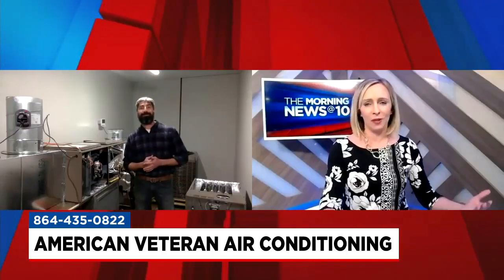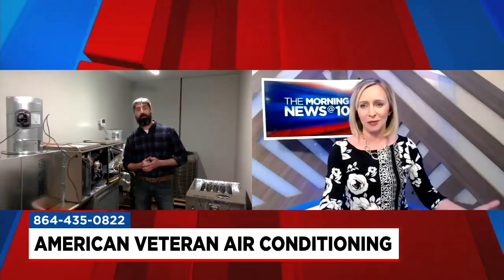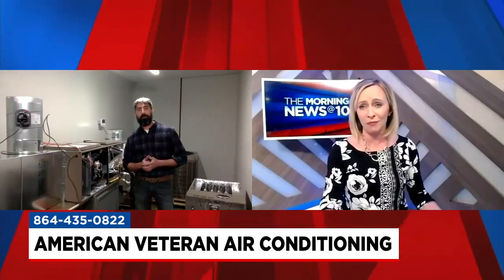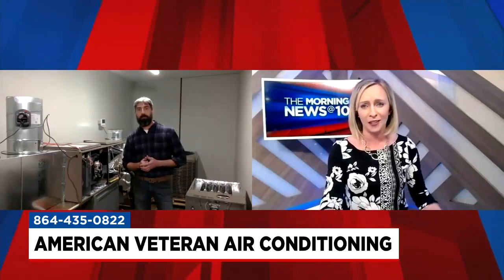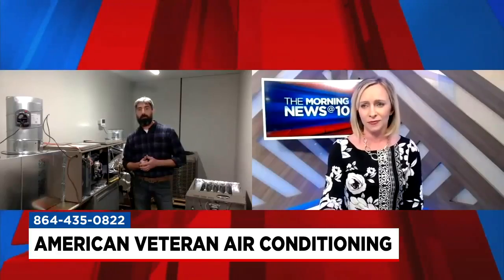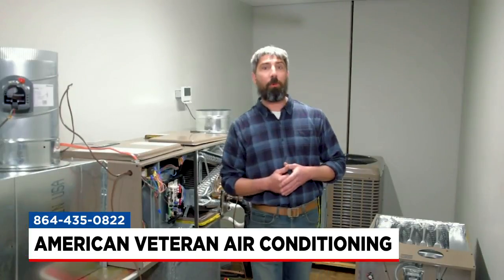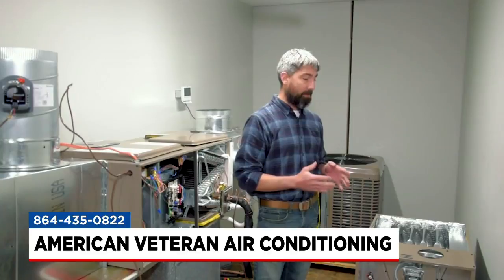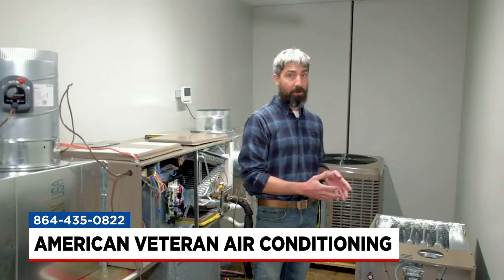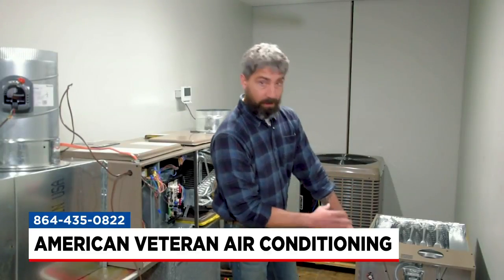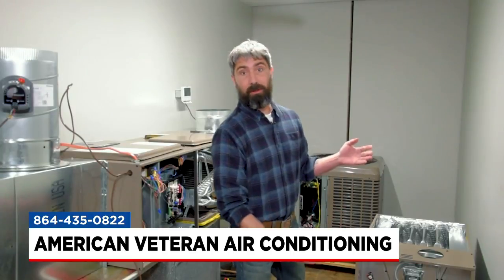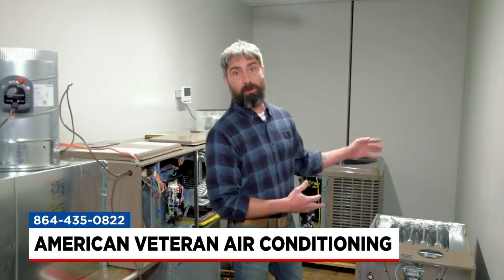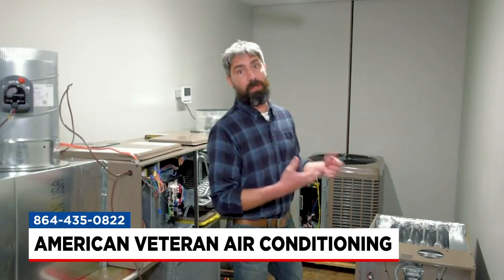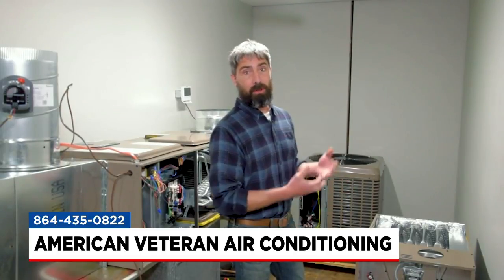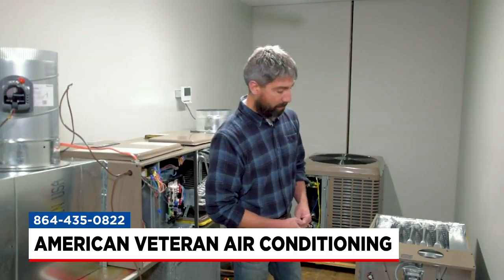And you definitely want to keep people comfortable. You don't want their systems to just shut off, but safety is a big component because you don't want any combustible gases coming into the vents, right? Absolutely, and that's when we roll into the furnaces, and there's a lot of things that we check on a furnace. Ideally, first thing we're doing, again, is checking airflow. Airflow is the key to everything that goes across that system. If it's not getting the proper amount of air across it, then it's not going to operate properly.